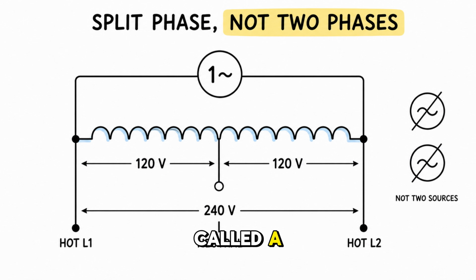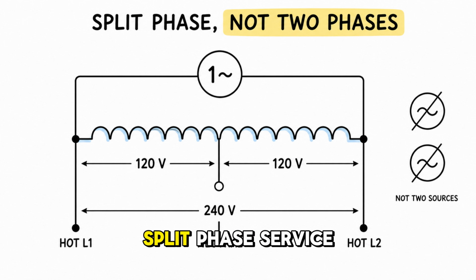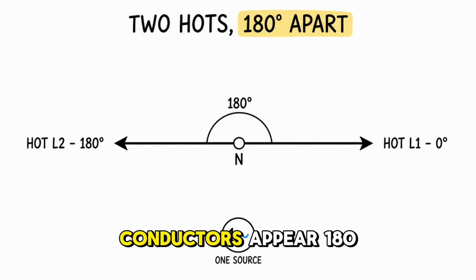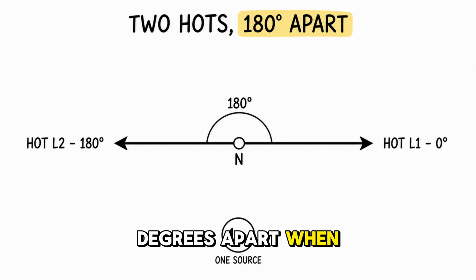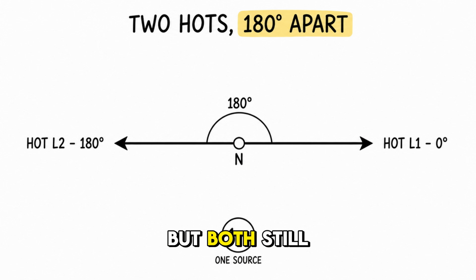This arrangement is called a 120 and 240 volt split phase service. The word split matters because the transformer has not produced 2 independent phases. It has divided one secondary winding around a center connection. The 2 hot conductors appear 180 degrees apart when measured relative to neutral, but both still belong to one single phase source.